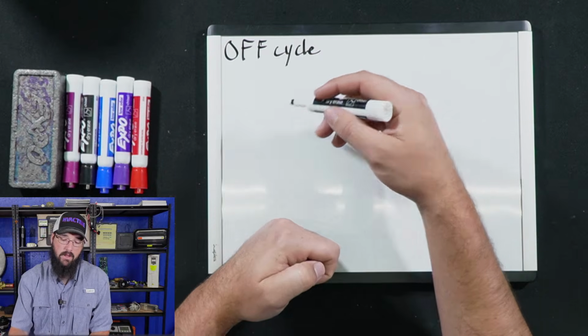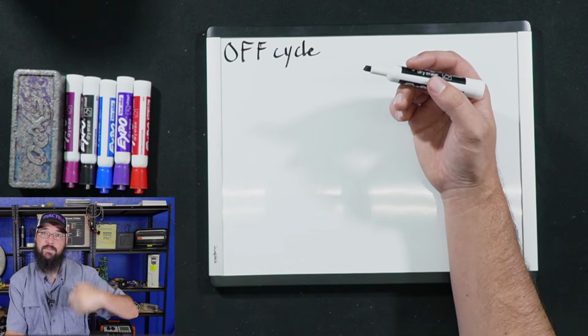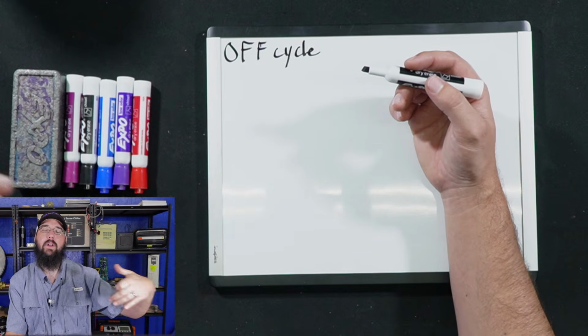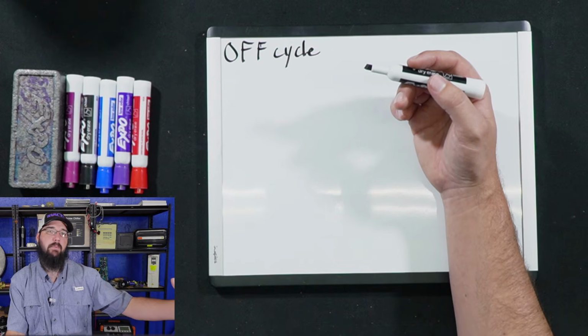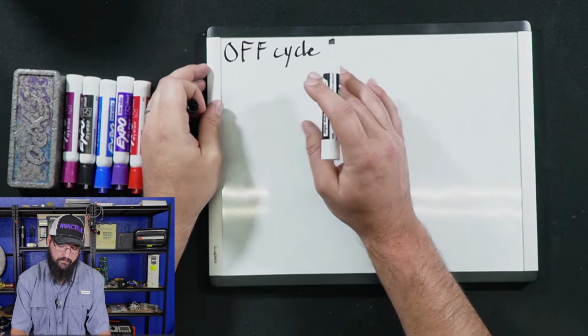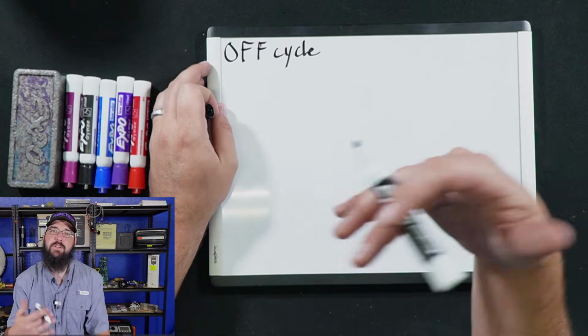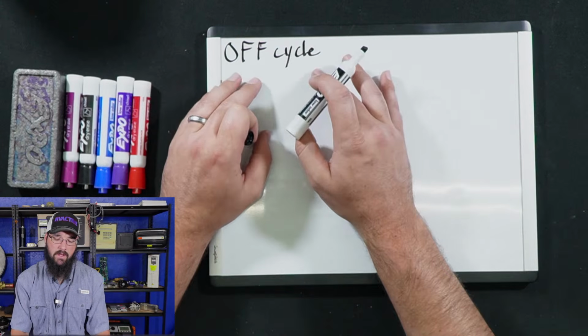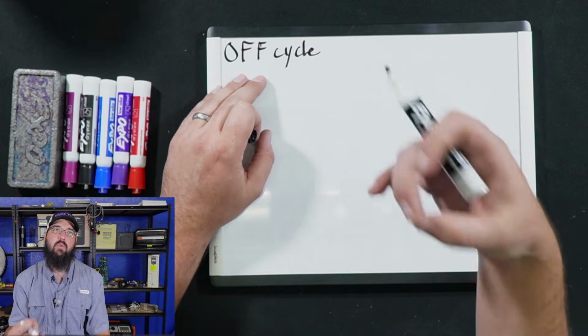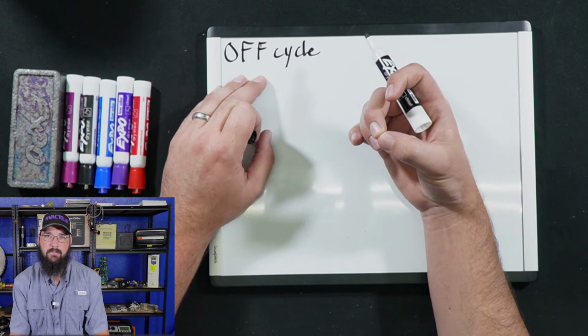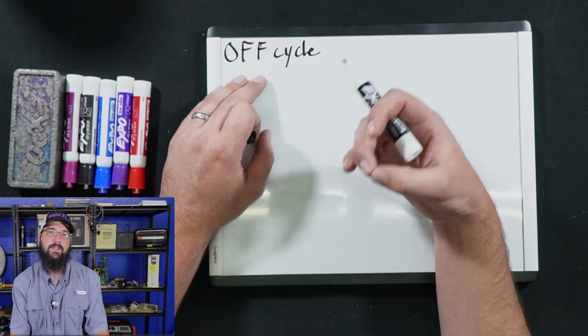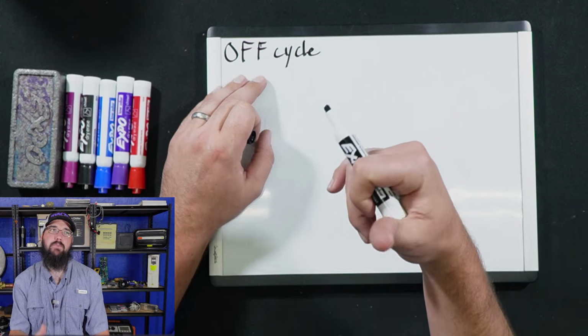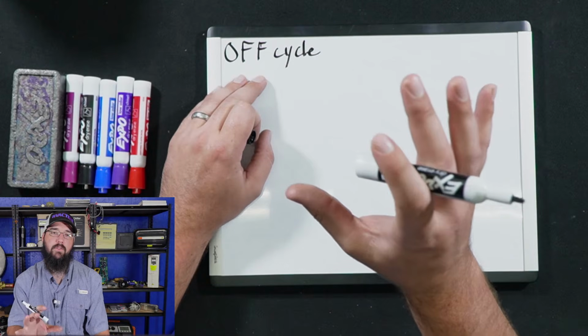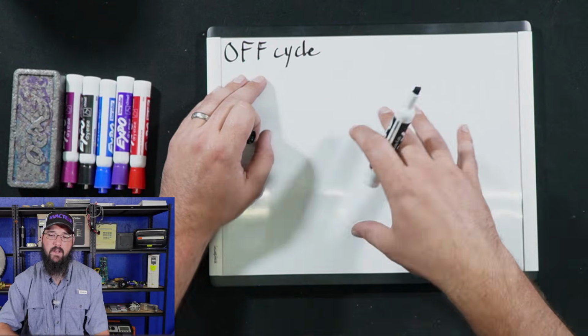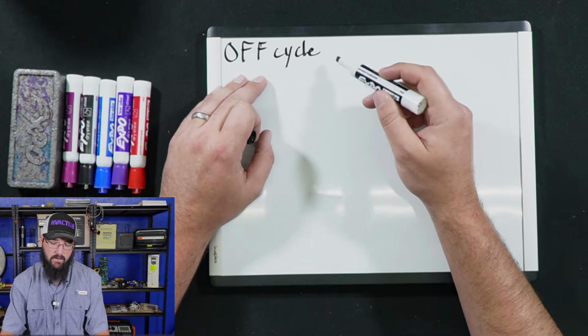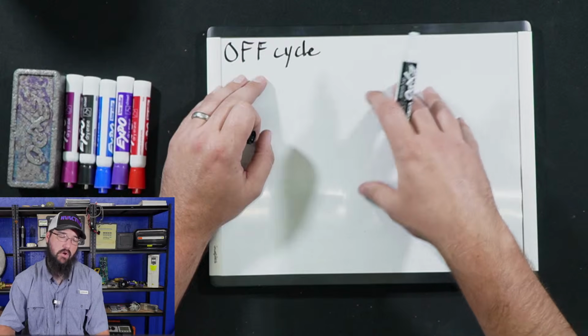It's a pain. I've also seen it during the off season, if your plant gets really cold, it'll get the evaporator to stay cold and it'll draw that oil off. Anyway, so you could have an off-cycle migration. Now, most of the time with an off-cycle migration, I would say it's more common that the oil heater itself is not functioning correctly, or we somehow got a ton of refrigerant into the oil sump, which could be an eductor issue where the eductor is getting overfed on the refrigerant.